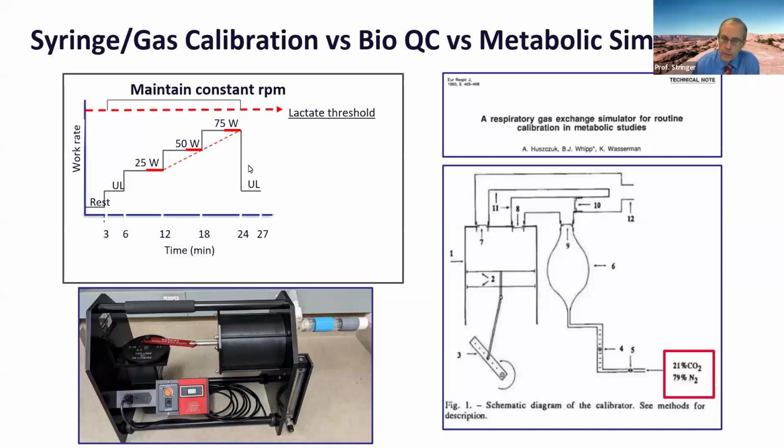But the biological calibration doesn't require this type of equipment. It can be done with just an individual in your lab. So that's the beauty of that. Okay, so that's biological calibration versus metabolic simulator.